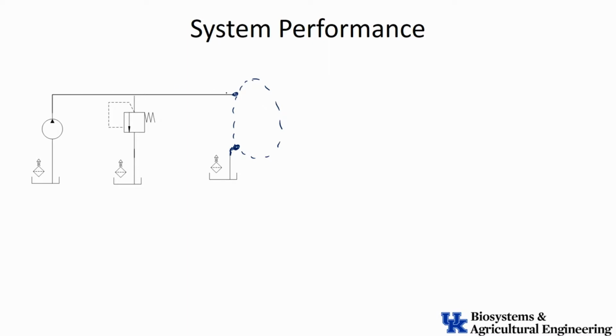So the flow is coming down out of here, but I've got this relief valve in there that's protecting the system. The idea is, if this system pressure gets too high, this sensing line here says, open the relief valve, let's allow that flow to come back to the reservoir. This pump is cranking out flow, it's pushing stuff. If it doesn't have enough place to go downstream and the pressure gets too high, we allow some of it to sneak straight back into the reservoir, and that keeps my system pressure from getting too high and protects me.